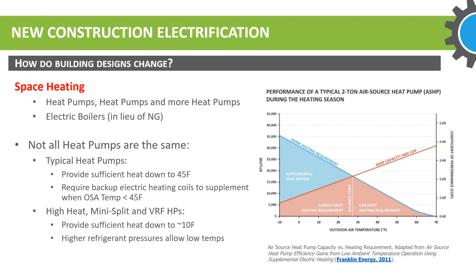This is in general. It all comes down to who's selecting the equipment. Someone can absolutely mess up and select the wrong equipment, so this does not eliminate the need for knowing what you're doing. But in general, those systems work out. Now, in our areas, the design condition for heating is between 11 and 17 degrees. So if you can make it down to 10 at 100% capacity, then you're fine. What that eliminates is a need for additional wiring and additional electrical capacity for an electric resistance heat strip in your unit. So if we can go to the next one.